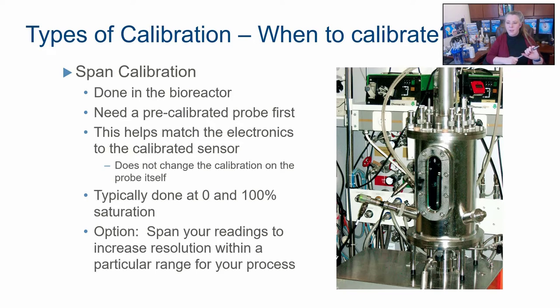Zero cal. Now we're going to do 100% saturation. And how do you do that in a bioreactor? Just like you did with the nitrogen, except you're going to do it with oxygen or air purge. Again, you can do it either way, either a set sparger, set time like I did, only you're using oxygen gas, or hook this up, watch it go up until it goes all the way to the top and it's flat and it stays stable for about 5 minutes and it's maxed out. You say, that's 100%. And now you've done your span calibration.